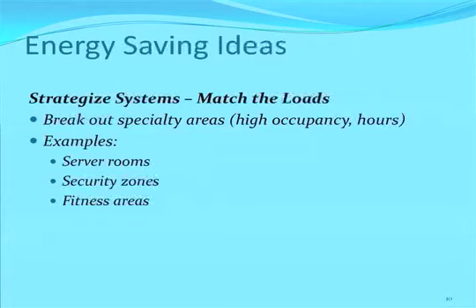Moving on to the systems level. First approach is match the loads with your systems. And that is breaking out specialty areas that are the minority load for your building, but sometimes have longer run hours or have high occupancy that's intermittent. For example, server rooms tend to be a very good application here to maybe have that served by an entirely different cooling system so that you're not dragging your whole building chiller into availability around the clock because you have a server room on the first floor.